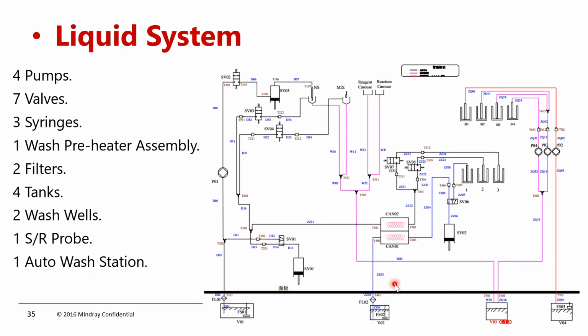So just to understand, black lines are water. This pink line is diluted waste, meaning low concentrated waste, and the blue line is a detergent line, and the red one is a high concentration waste. Okay, so this is how washing takes place. Each probe will wash the same cuvette two times. So probe number one dispenses and aspirates, again dispenses and aspirates. So it washes the cuvette with the detergent two times.